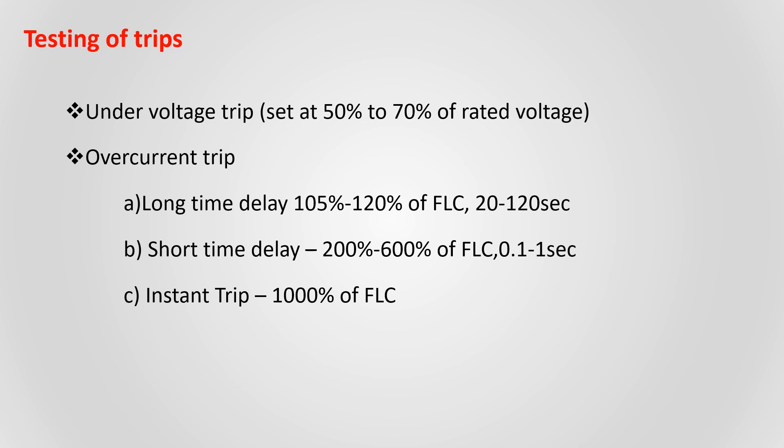This trip can be tested by voltage injection method. Overcurrent trip is due to the overload of the generator, so it can be tested by current injection method. The time delay in overcurrent trip depends on the percentage of full load current. Both overcurrent trip and undervoltage trip tests are done by shore technician.